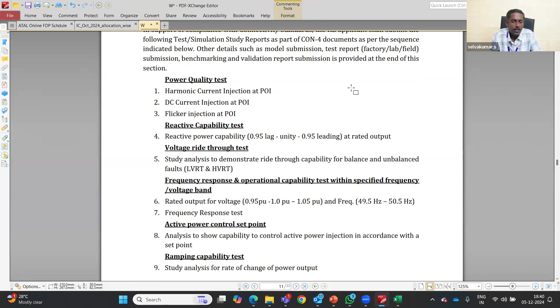Power quality you have to do using a detailed EMT model. Reactive power assessment carried out in a detailed RMS and equivalent EMT model. And the rest of the things - voltage ride through, frequency response, active power, ramping - all these have to be carried out by both RMS as well as EMT, but it's an equivalent model.